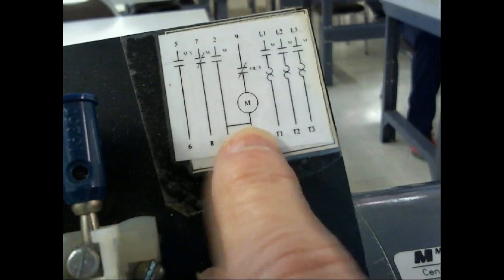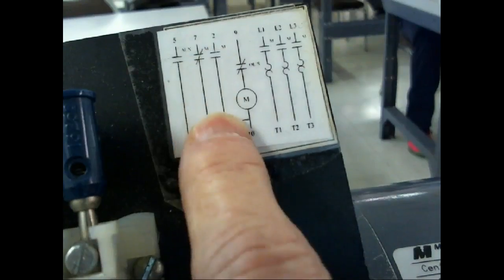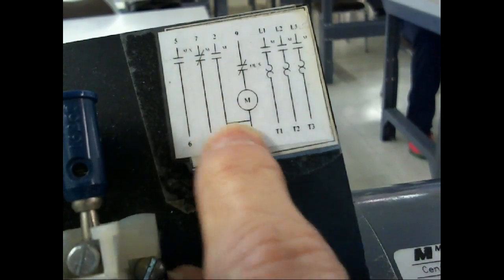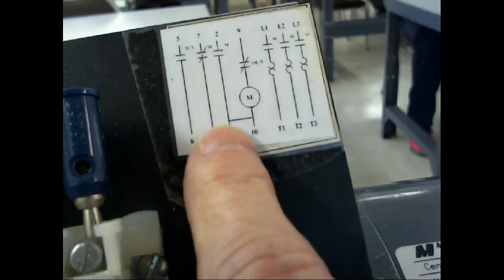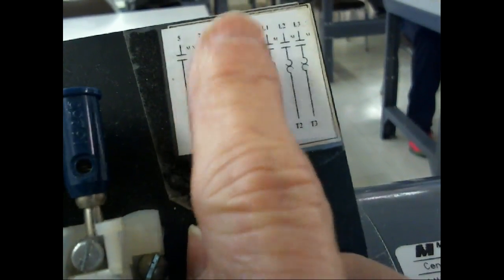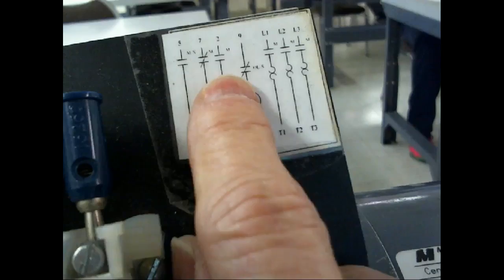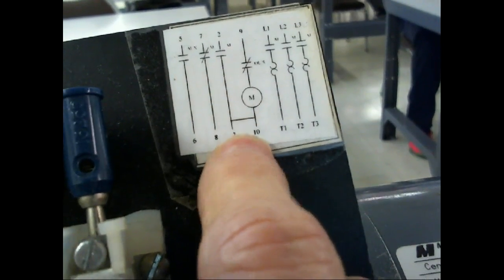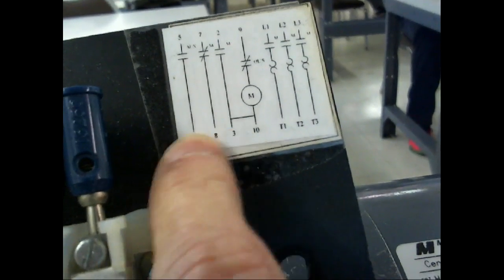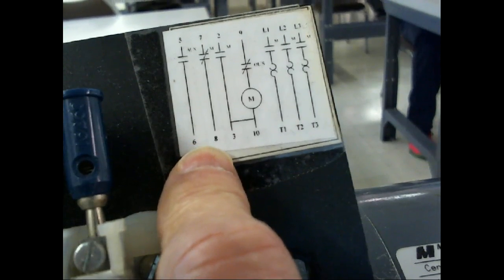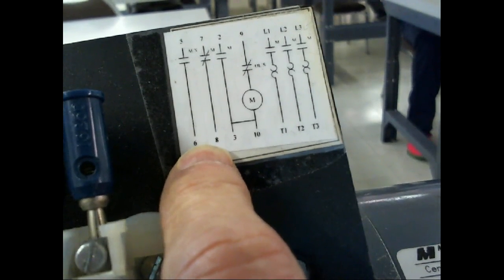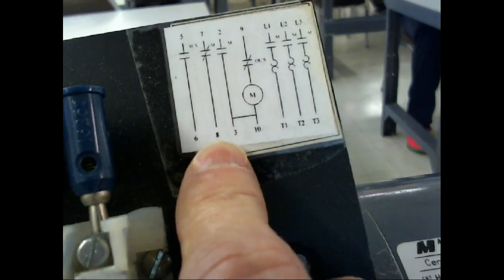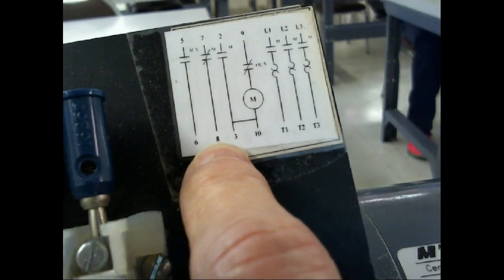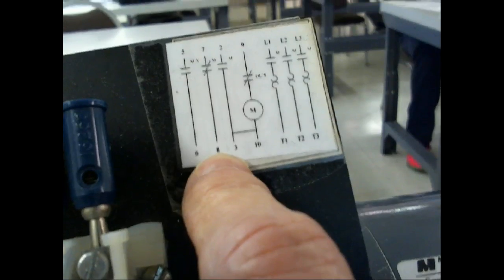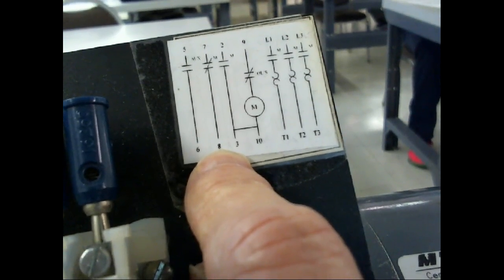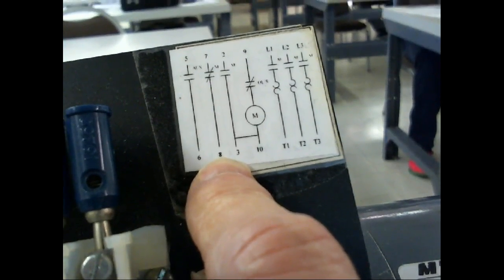When ECI wired this up, they wired in this right here so we could use it as a sealing circuit, but we're not going to be able to do it on the reverser because we've got to put a normally closed contact in there. So don't use 2 to 3. So we have a normally open contact right here between 5 and 6. We can use that to seal it in. And here's that normally closed contact between 7 and 8 that we can use in the other relay circuit. You understand?